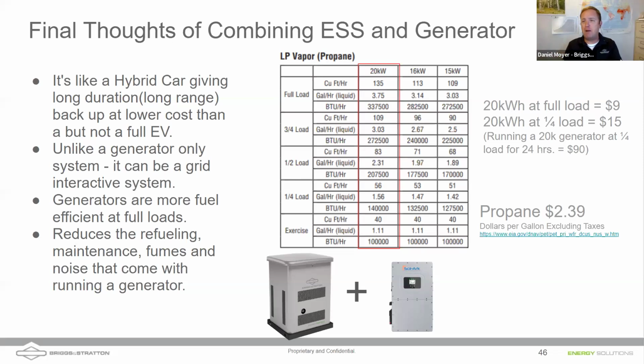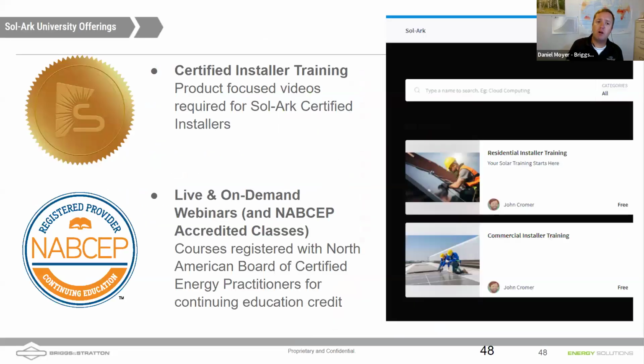Nathan, being a professor, probably would have wanted me to show my math here a little more, so I'll come back and adjust this. But if you run the generator at a quarter load, you're still using a gallon and a half at $2.39. If you run it at half load, you're using 2.3 gallons an hour, and if you double that load, you're up above 3. So the takeaway here is: run the generator hard, reduce the amount of fuel, reduce the maintenance, reduce the fumes, reduce the noise that induces anxiety, and provide the homeowners with a more resilient system.